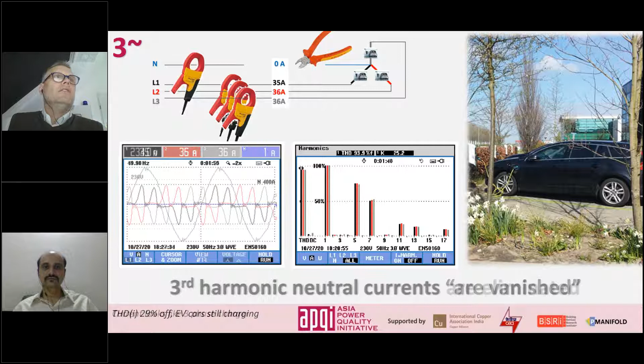So when I'm looking at this harmonic picture, I'm seeing the 5th and the 7th harmonic. That means the grid is looking at a charger which would have 6 diodes, or a 3-phase charger it would be. On the left side you see the voltage and the current, and when the neutral wire is cut or melted down, the grid will look at it as a 3-phase charger, and that's why the 2 bulbs are there.